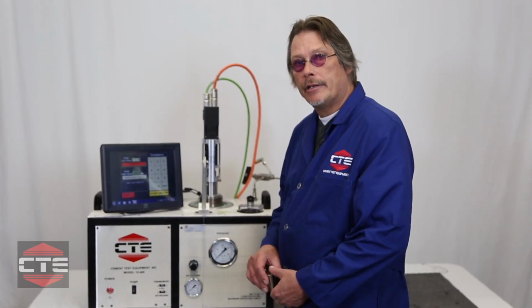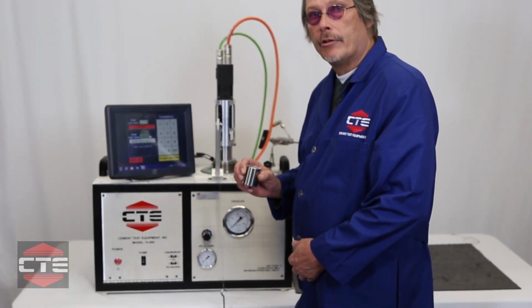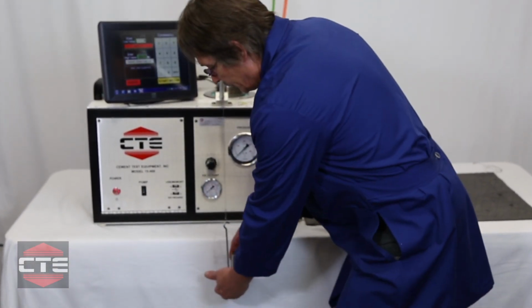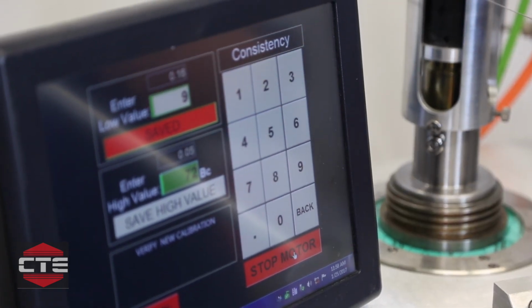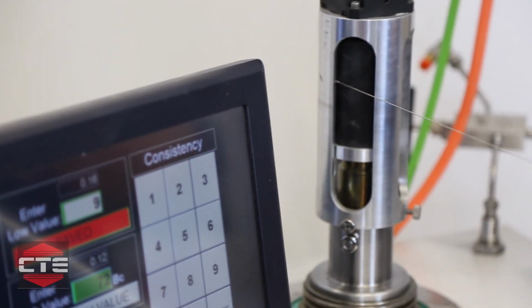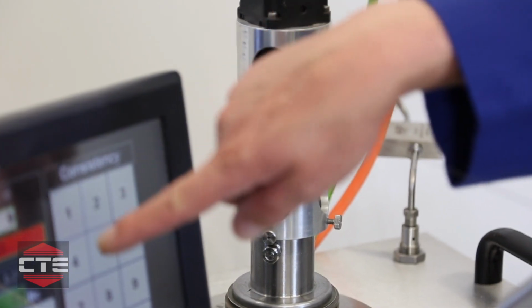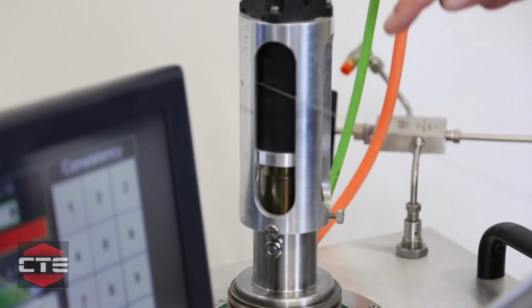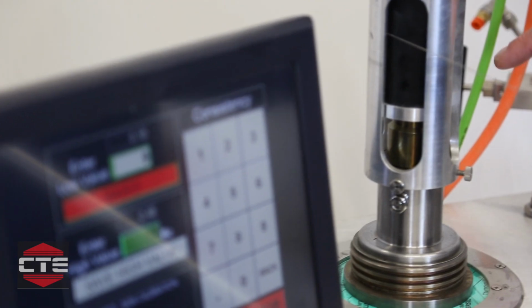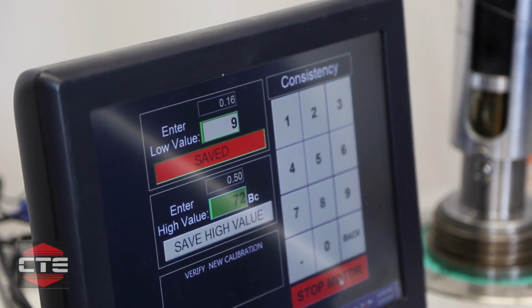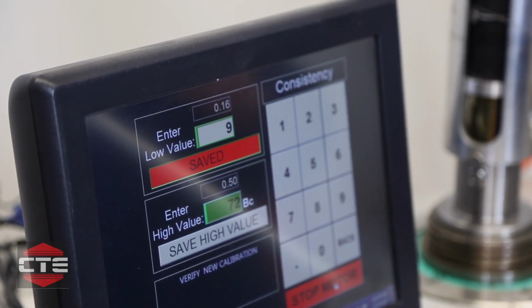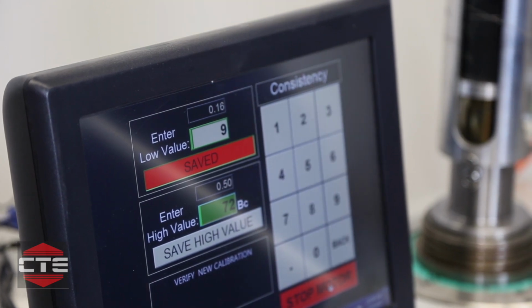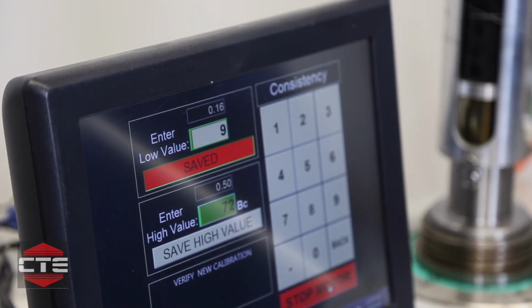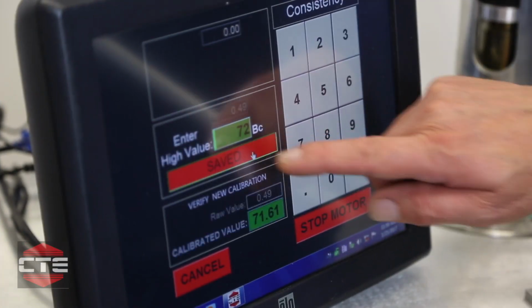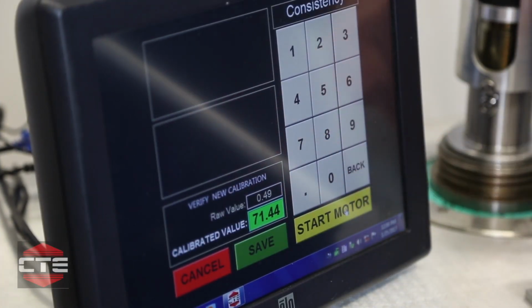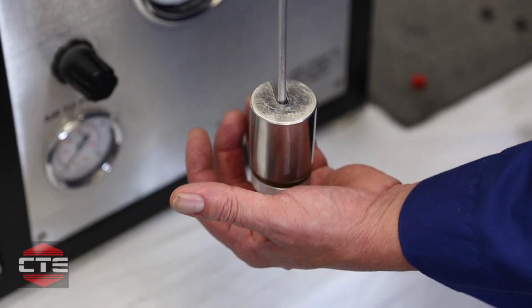Now that we have our low value calibrated, we're going to add 500 grams of weight for a total of 600. Start motor and let the motor wind the weights up again. If you look at your raw value, it's all over the place until it makes at least one revolution of the mag drive. After the revolution, you'll begin to see the raw value settle into one value, and that's the value you want to capture for your consistency calibration. Save, stop motor while supporting the weights, or you will be chasing these weights.